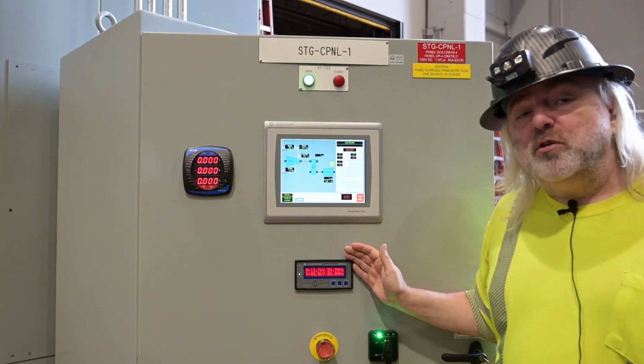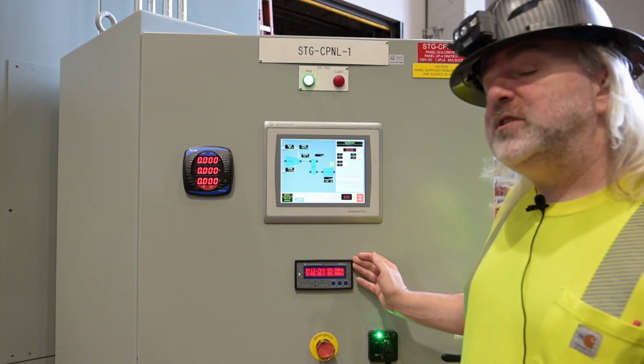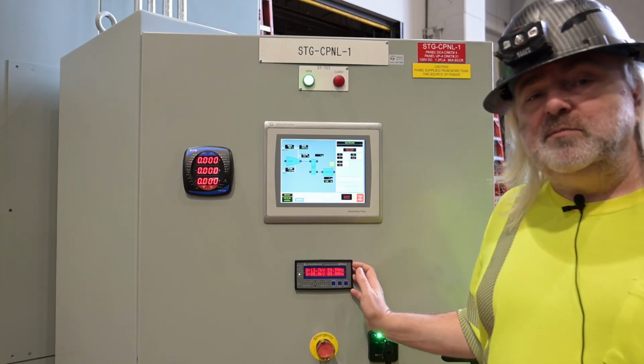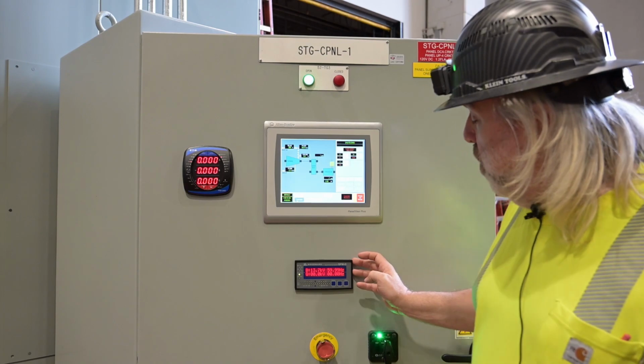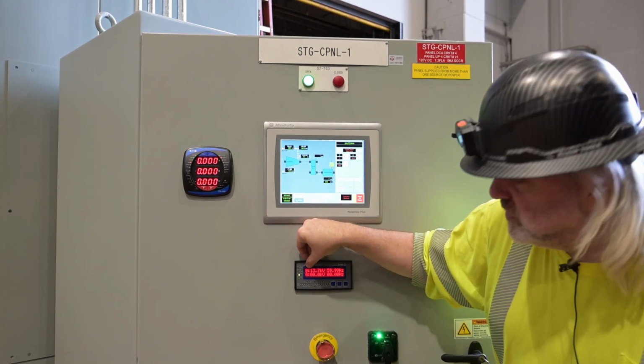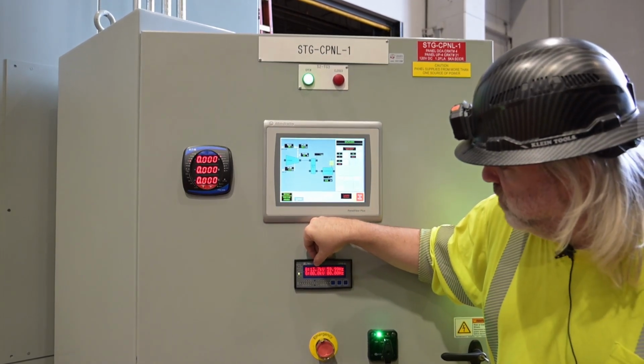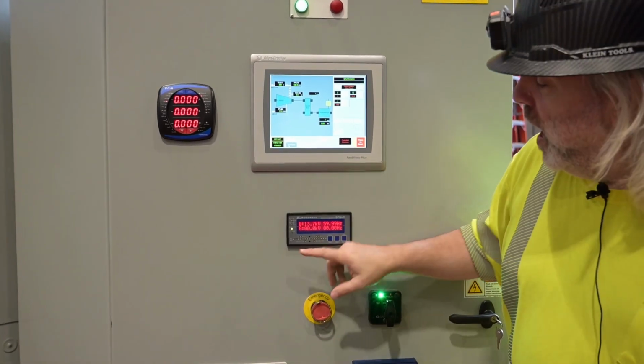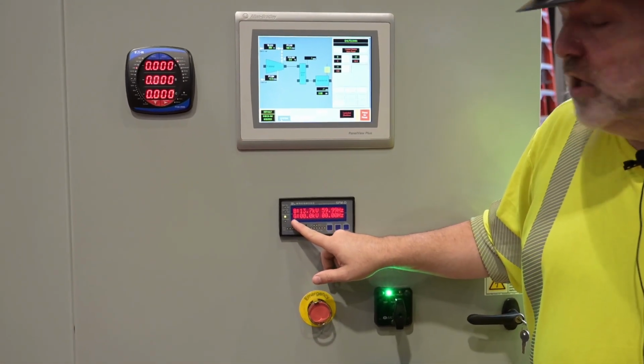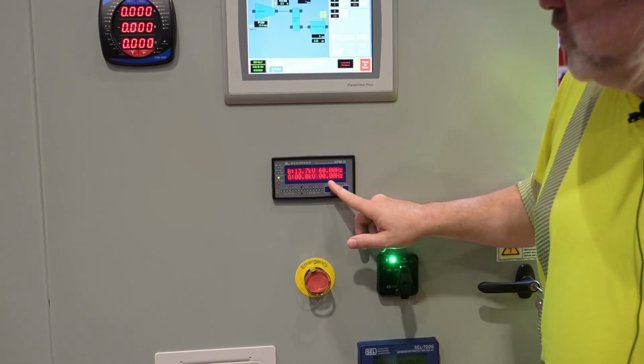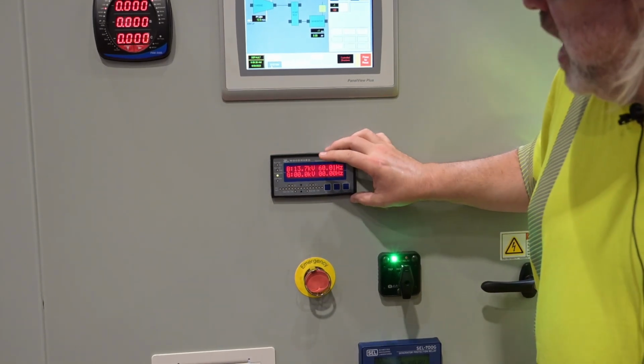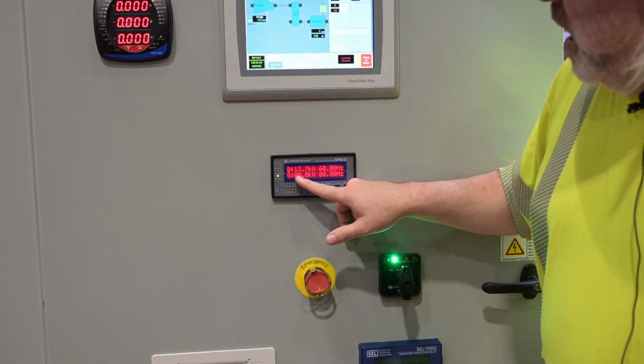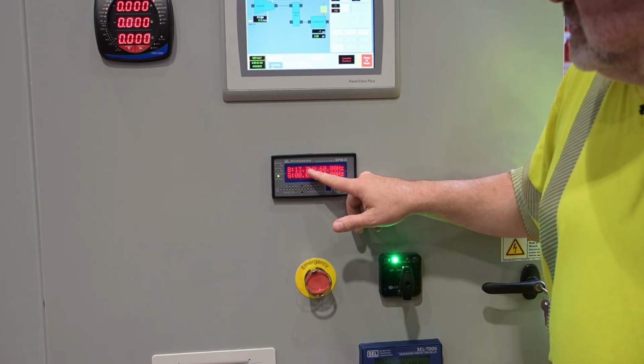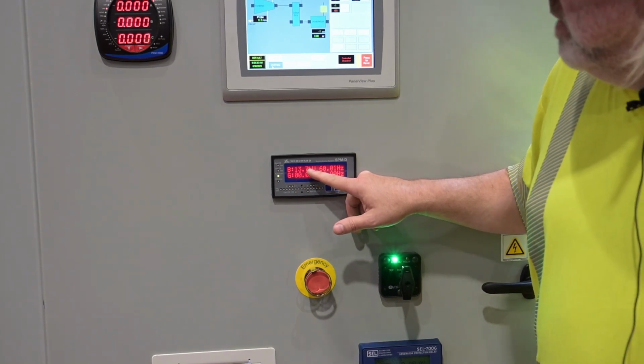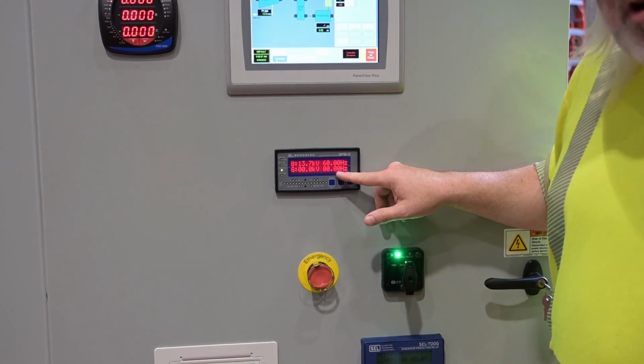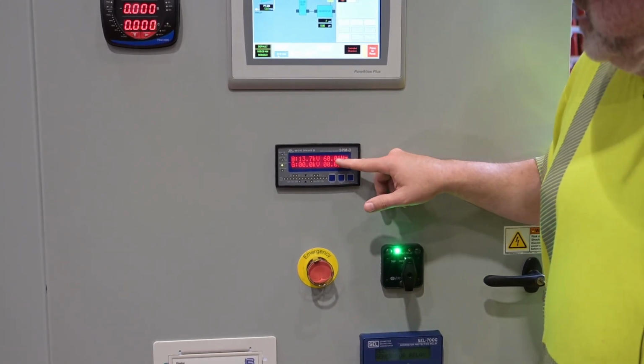Right here is our auto synchronizer. This device is what's going to be used to synchronize our system to the utility. At the top, we have our bus, B for bus, with our voltage and our frequency. Underneath, we have our gen, G for generator, voltage and frequency. When we go to synchronize, we'll be at rated speed. Our generator voltage will be slightly higher than the bus voltage, and our generator frequency should be slightly higher than the bus frequency.